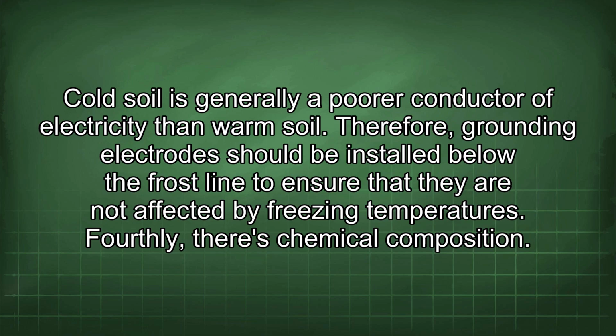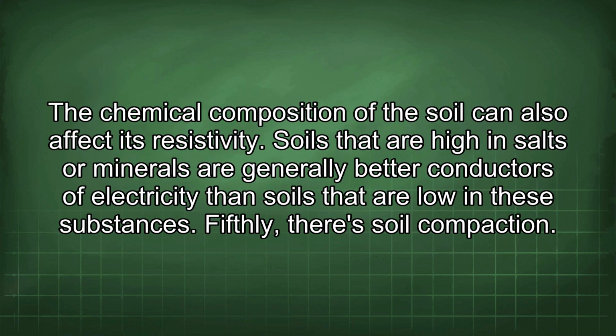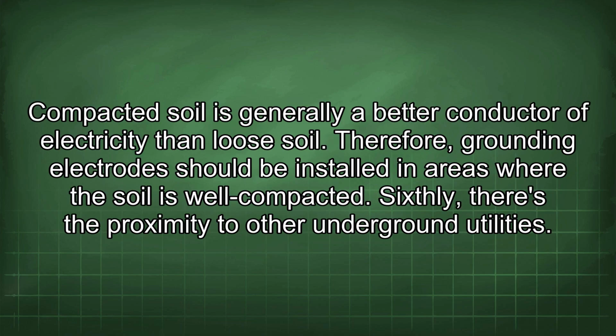Fourthly, there's chemical composition. The chemical composition of the soil can also affect its resistivity. Soils that are high in salts or minerals are generally better conductors of electricity than soils that are low in these substances. Fifthly, there's soil compaction. Compacted soil is generally a better conductor of electricity than loose soil. Therefore, grounding electrodes should be installed in areas where the soil is well compacted.